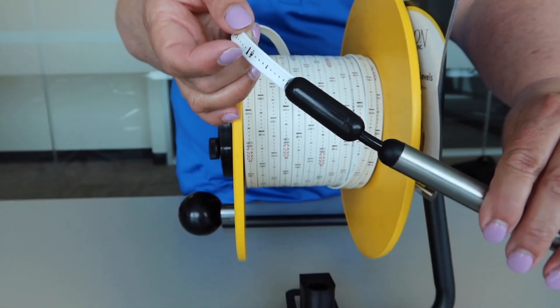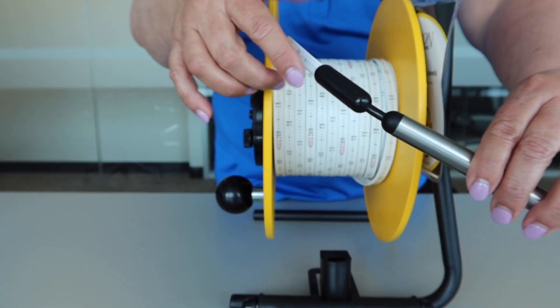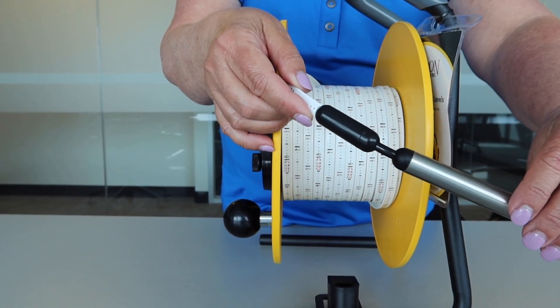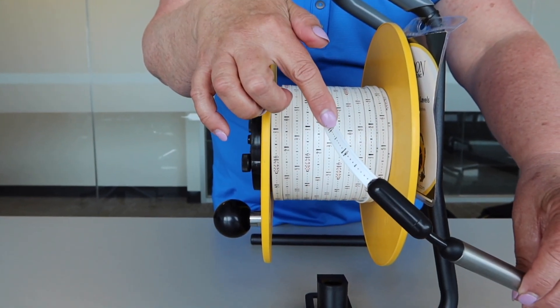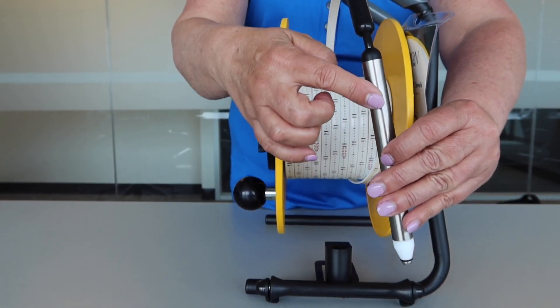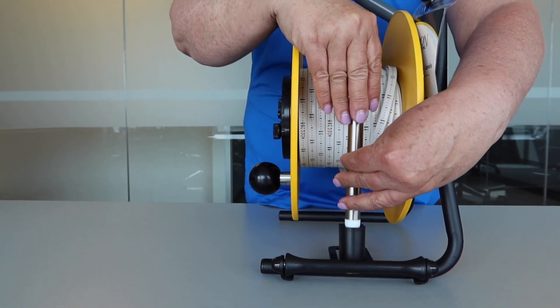There is a shear pin style linkage above the probe, which will break away if your probe gets stuck in the well. Better to save your more expensive tape and lose the probe, both of which are modular and replaceable as shown in our parts list.